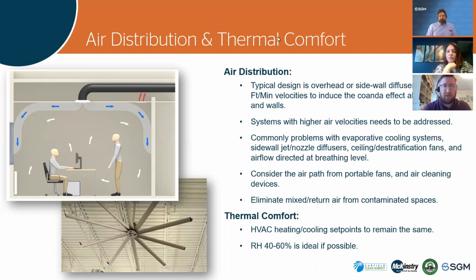And someone also had a concern about return air, mixing return air. This is something we definitely want to eliminate for specialized spaces. And what I'm thinking is like isolation rooms or nurses' offices. We deal with a lot of schools, so those are a couple of spaces where we're going to go ahead and not return air and mix it into the supply air that's distributed into the building. But in other spaces, that's typically not a massive concern at this point.